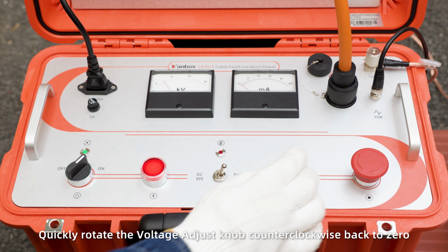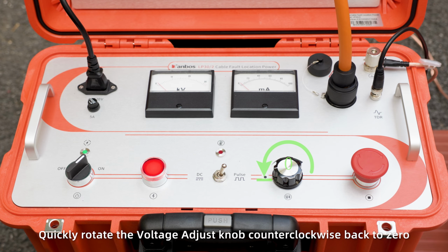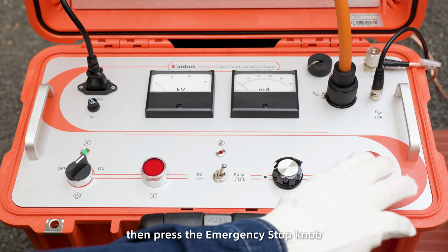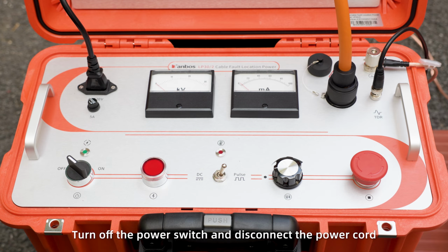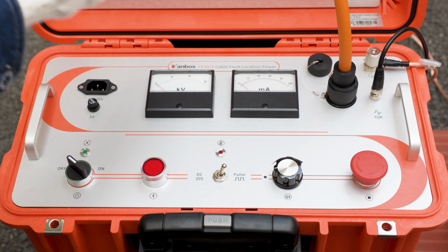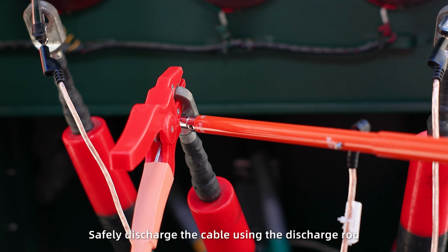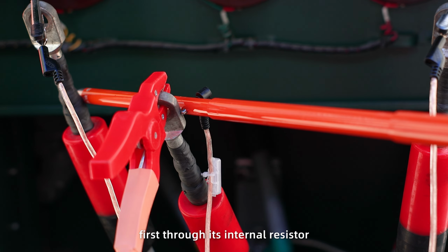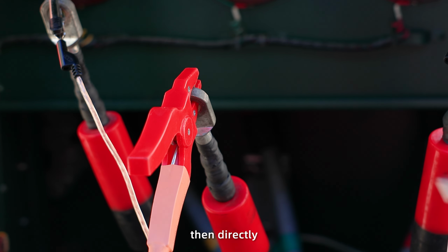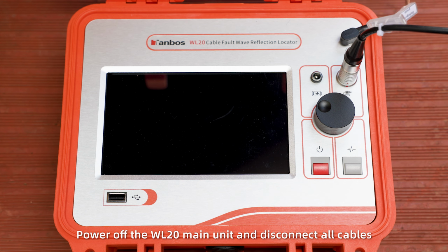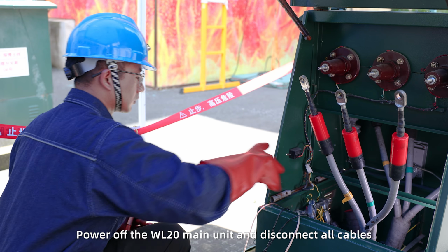Quickly rotate the voltage adjust knob counterclockwise back to 0. Then press the emergency stop knob. Turn off the power switch and disconnect the power cord. Safely discharge the cable using the discharge rod, first through its internal resistor, then directly. Power off the WL20 main unit and disconnect all cables.